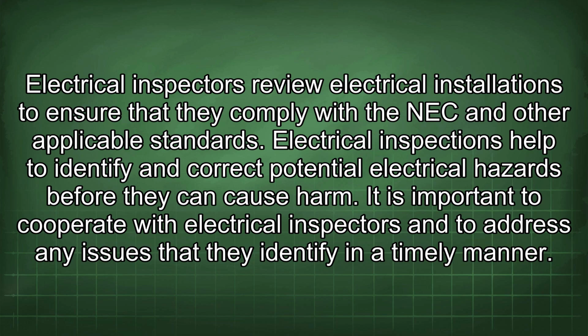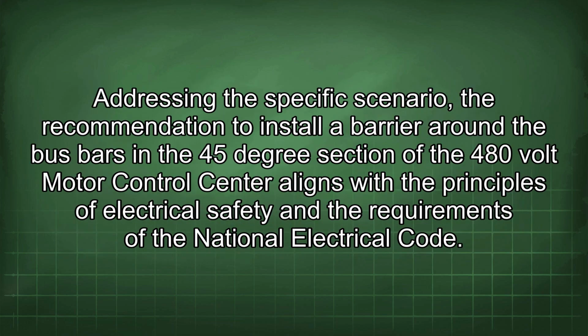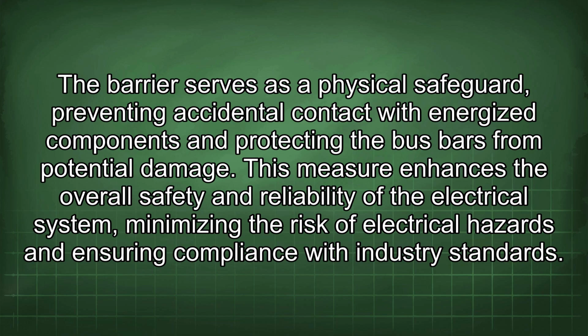It is important to cooperate with electrical inspectors and to address any issues that they identify in a timely manner. Addressing the specific scenario, the recommendation to install a barrier around the bus bars in the 45-degree section of the 480-volt motor control center aligns with the principles of electrical safety and the requirements of the National Electrical Code. The barrier serves as a physical safeguard, preventing accidental contact with energized components and protecting the bus bars from potential damage. This measure enhances the overall safety and reliability of the electrical system, minimizing the risk of electrical hazards and ensuring compliance with industry standards.